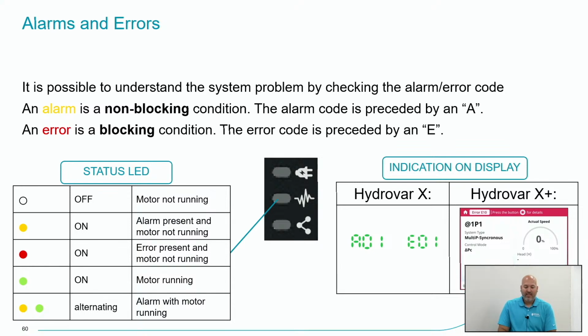Okay, I'm circling back. Like I said, an error is a blocking condition. It's going to actually shut down the unit and require somebody to resolve whatever that problem is before it will become operational again. To avoid nuisance tripping or to prove a fault, an error will actually try to reset itself a few times. And if it fails after a few failed attempts and it continues to see that error, that's when it completely shuts down the system. But it will try to reset itself a few times, and after the third time, if it has failed, it's going to shut down the unit just to protect it from damaging itself.